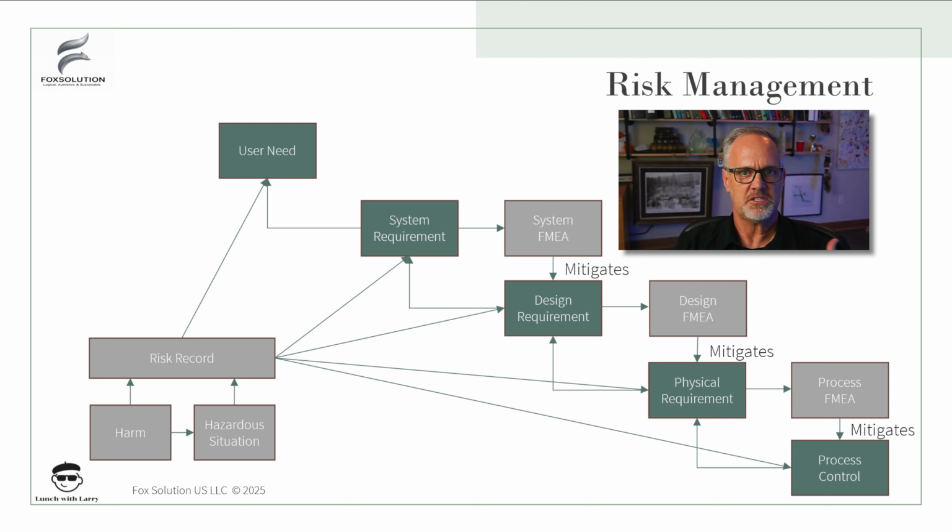And then this sterilization question I had, how often the harm is exposure of the user to a non-sterile device. There's all kinds of things that need to happen to assure that that hazardous situation where that exposure happens doesn't occur. So things from aseptic transfer techniques, storage, the sterilization process itself, all the design requirements around the design of the sterile barrier bag, for example. So all kinds of things that we need to take into account when we say that we've controlled that hazardous situation. It really needs to be a systems level view.